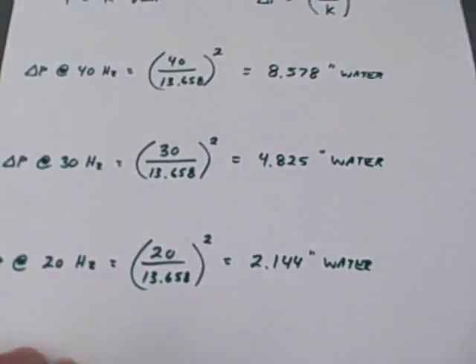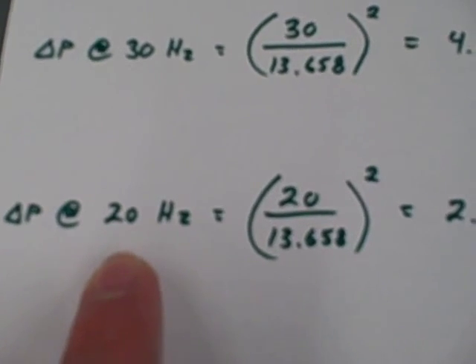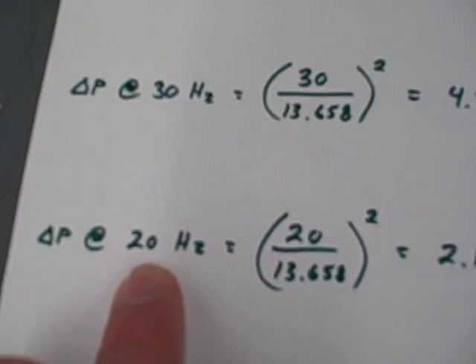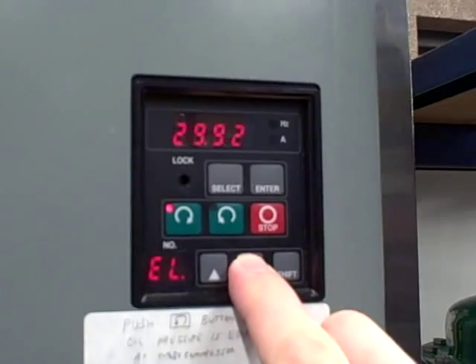Our next test is going to be to decrease the motor frequency down to 20 hertz. We predict a value of 2.144 inches of water given that new motor speed. We'll come over here and decrease this to 20 hertz.